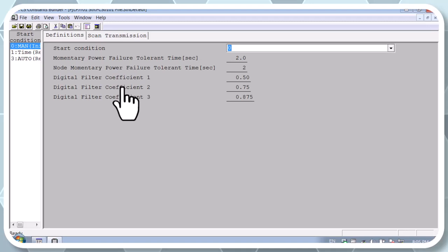And my friends, here we have 3 parameters. The 0 means you do not apply filtering, and when you set 1 it means that you use light filtering. 3 seconds means you apply medium filtering, and 7 seconds is strong filtering.